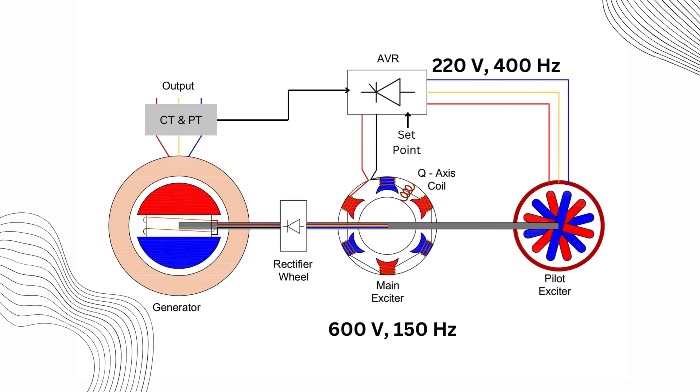In the brushless excitation system, rectification occurs twice. First in the AVR using thyristors and again in the diode rectifier wheel using diodes. This dual rectification process ensures a stable and reliable DC supply to the rotor.